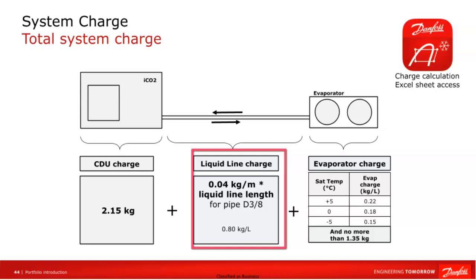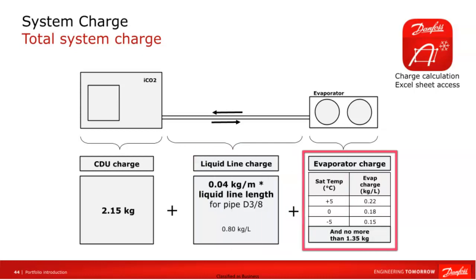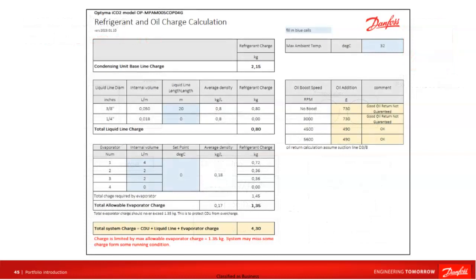The amount of refrigerant in the evaporator is calculated by multiplying the density of the refrigerant at a given saturation temperature by the volume of the evaporator. However, please remember that the amount cannot exceed 1.35 kilogram. After summing the amount of refrigerant in the condensing unit, liquid line, and evaporator, we obtain the total amount of refrigerant in the system. On this slide, we present an Excel spreadsheet that is a useful tool for calculating the amount of refrigerant and the amount of oil required in our refrigeration system.